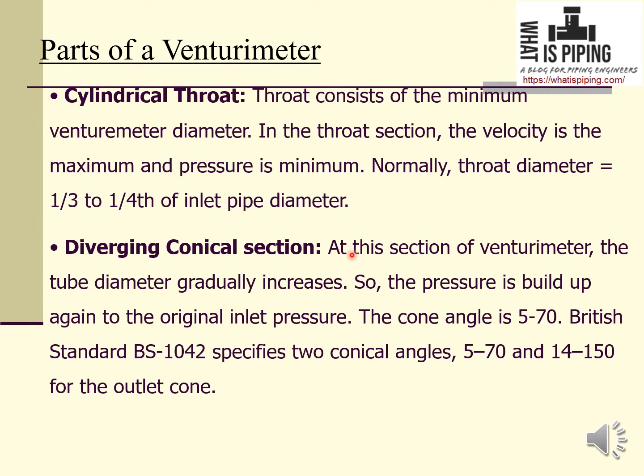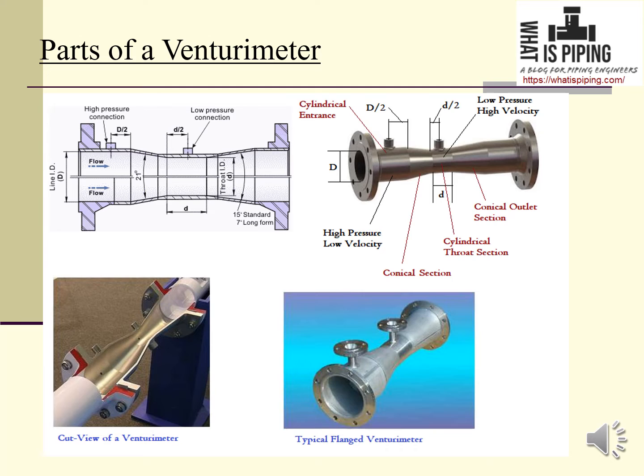In the divergent conical section, the tube diameter gradually increases so the pressure is built up again to the original inlet pressure. The cone angle is 5 to 7 degrees. British Standard BS1042 specifies two conical angles: 5 to 7 degrees, and 14 to 15 degrees for the outlet cone.